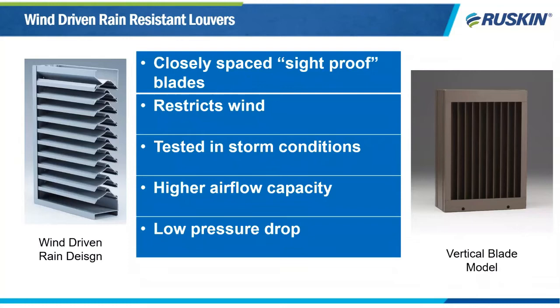So the better choice for outside air intakes are wind-driven rain-resistant louvers. These models feature closely spaced blades with special shapes that prevent wind from blowing straight through and capture and drain water away. They can be built with horizontal or vertical blades. Vertical blade models are actually the best at stopping rain as they simply shed water straight down the blades and out through the front. These products are tested in a wind-driven test, which is much more severe than the still air test used on standard louvers. And the blade profiles are typically made of smooth curves and hooks, which allows airflow across very easily and results in low pressure drop, and sometimes even lower per CFM than a standard louver.